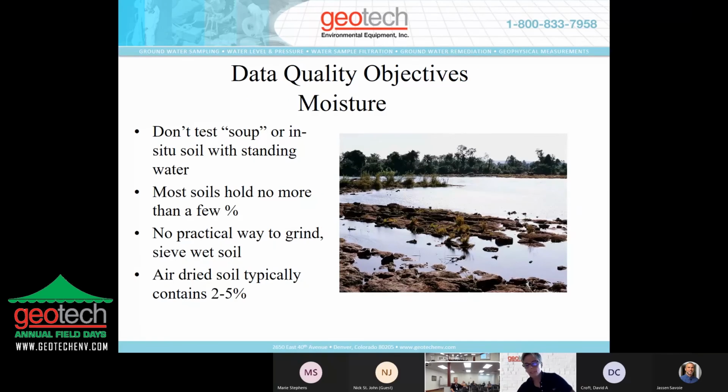So yeah, here's moisture. You want to make sure you're not shooting it directly into water or moisture. I've had folks shoot moisture samples. If you shoot them while they're moist, send them to the lab and get the data from them, then you can produce a fudge factor and identify, okay, we're going to just shoot it wet, knowing that it's this far off.